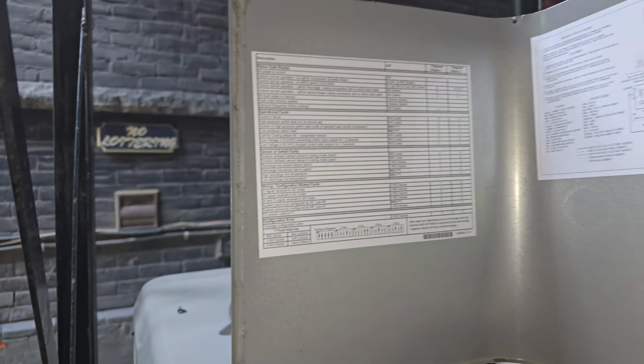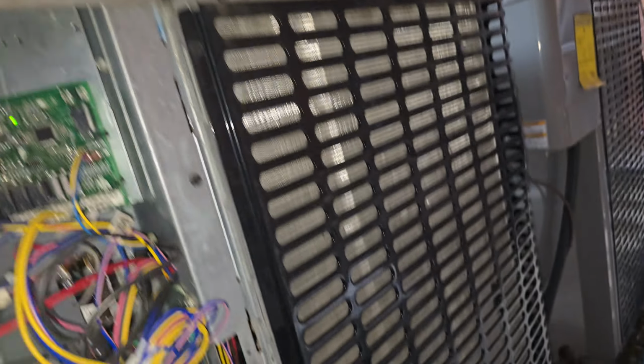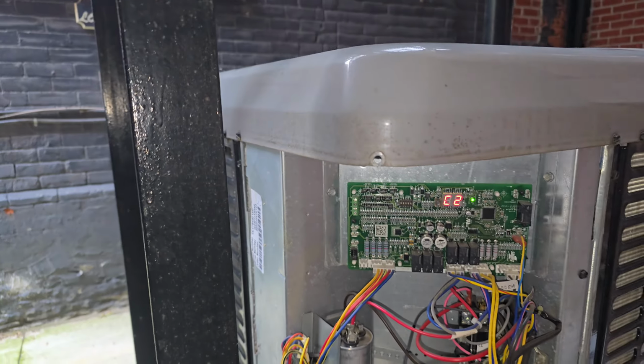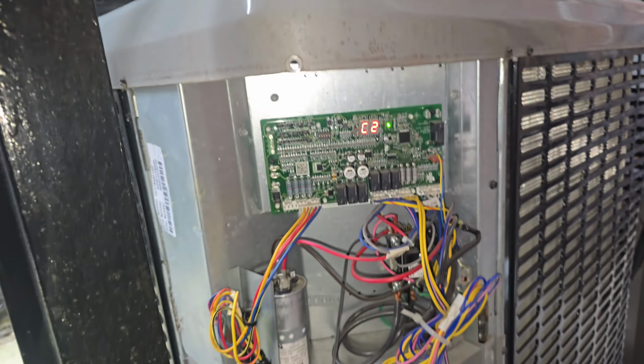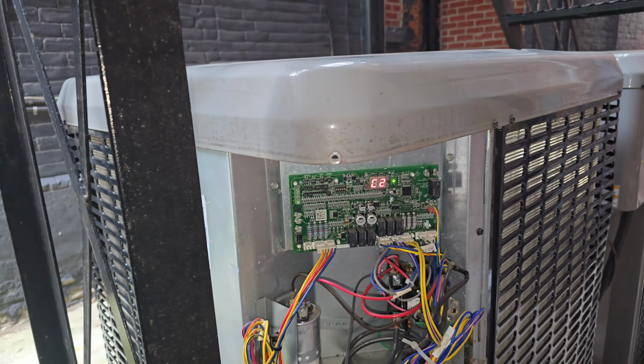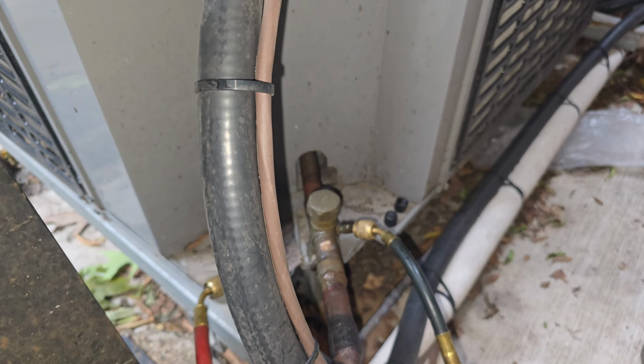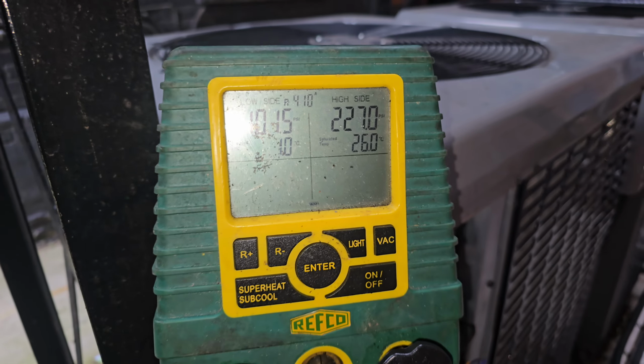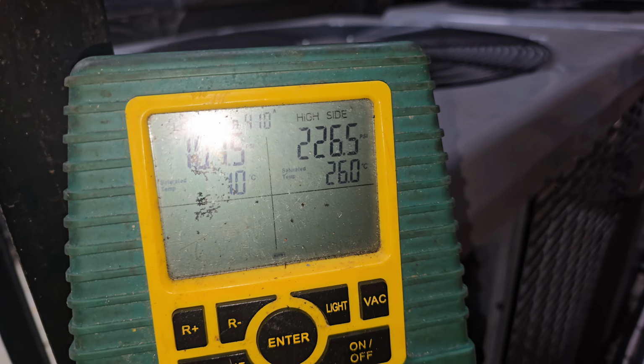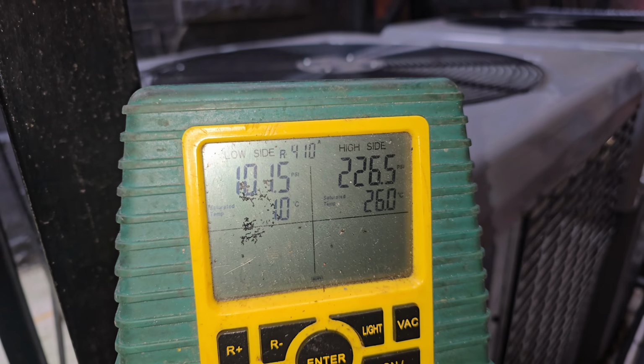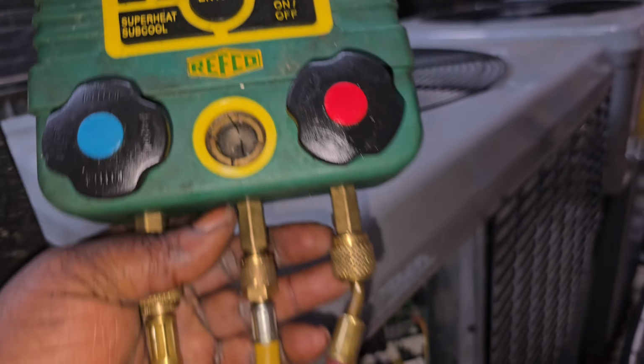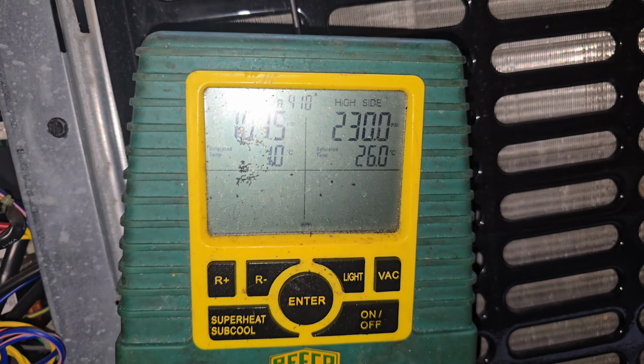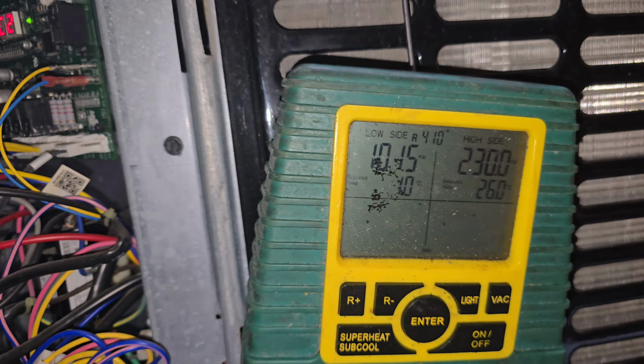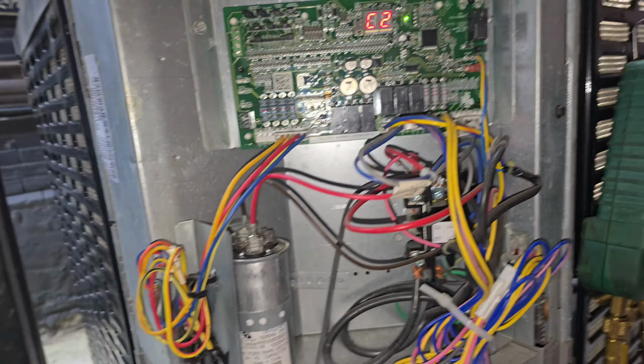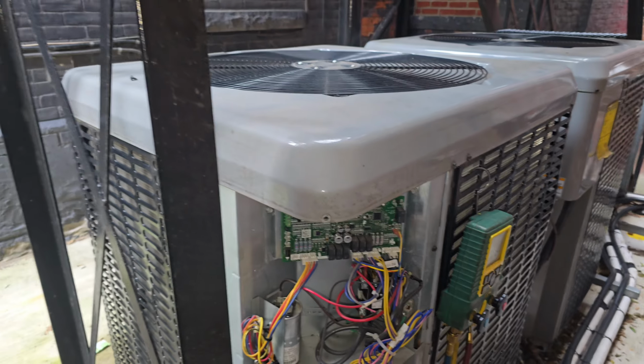But I recycled the unit again, turned it back on. The unit is coming on. Like I said, I went back again to get my gauges, and I just hooked up my gauges, so you can see. So here is my gauge. I'm getting 226 on the high side, and 101.5 on the low side. Yes, this reading isn't good enough. 230 is a little bit low. That shows low freon. But again, remember, this system is 410A.